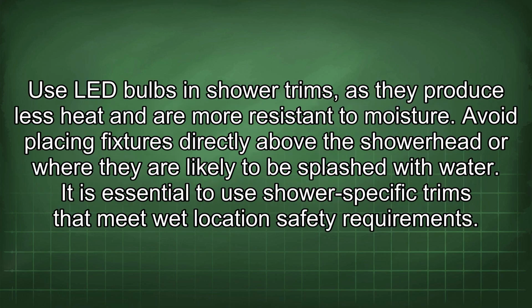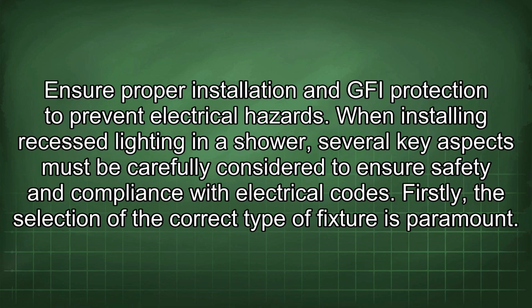Use LED bulbs in shower trims, as they produce less heat and are more resistant to moisture. Avoid placing fixtures directly above the shower head or where they are likely to be splashed with water. It is essential to use shower-specific trims that meet wet location safety requirements. Ensure proper installation and GFI protection to prevent electrical hazards.